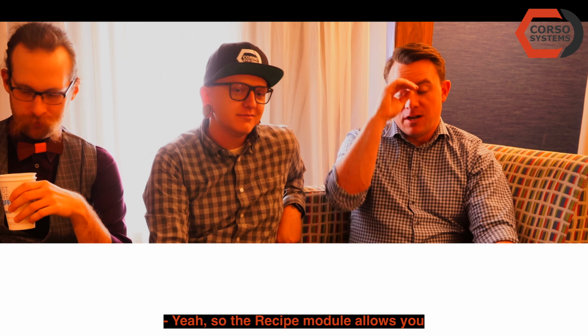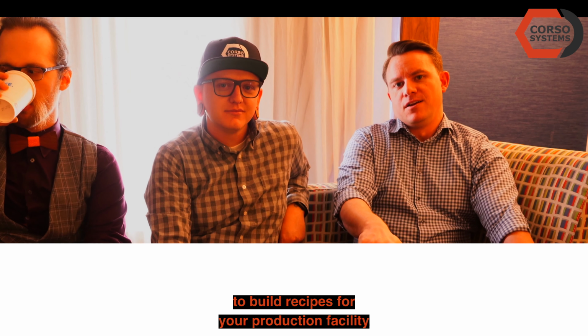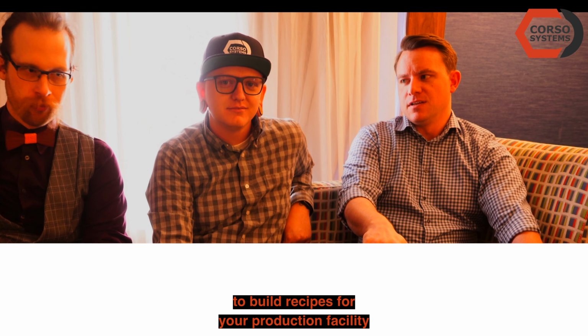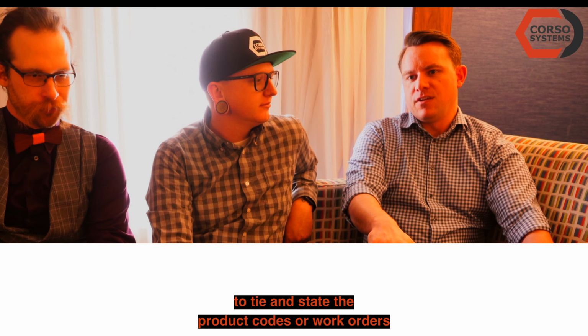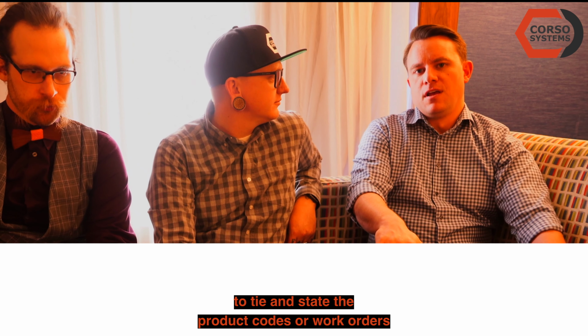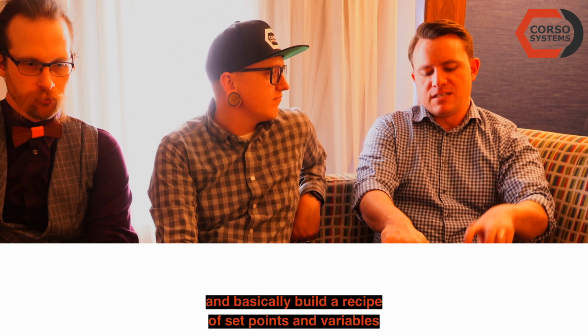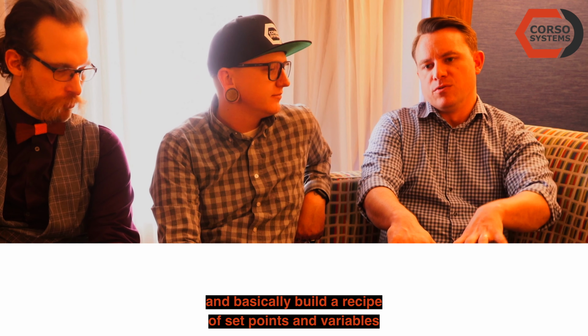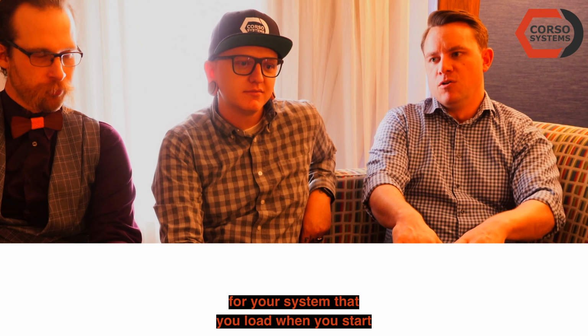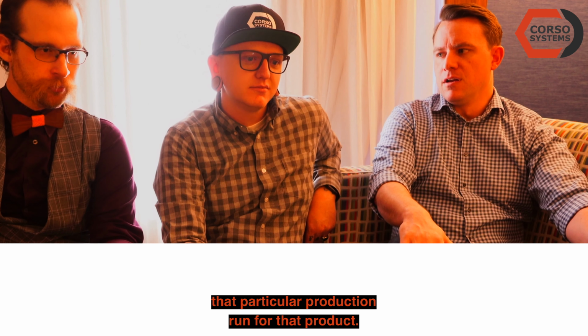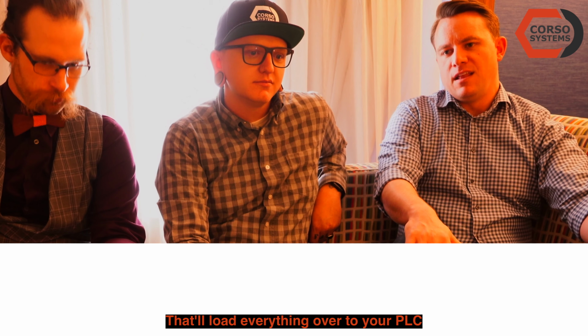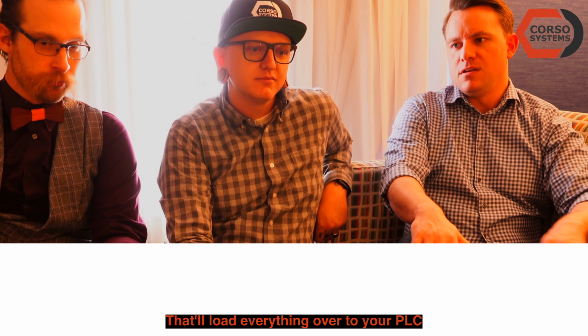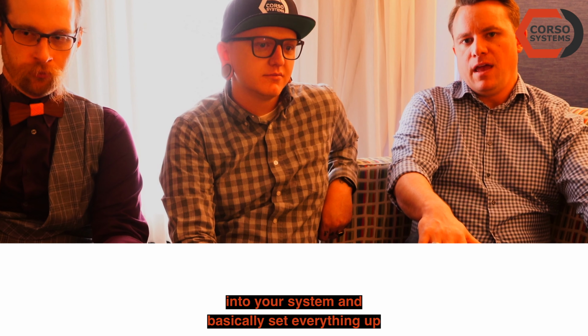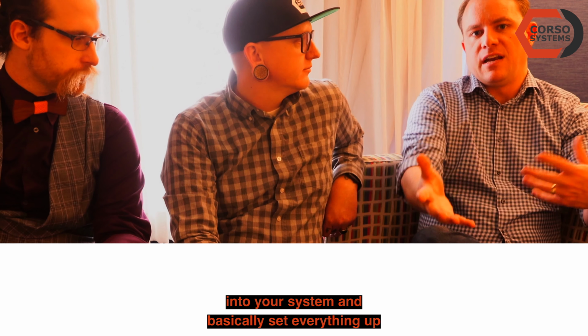Yeah, so the recipe module allows you to build recipes for your production facility to tie, say, to product codes or work orders, and basically build a recipe of set points and variables for your system that you load when you start that particular production run for that product.